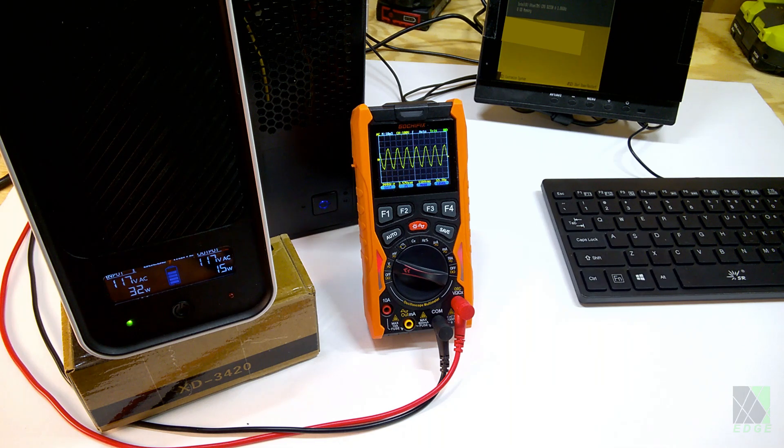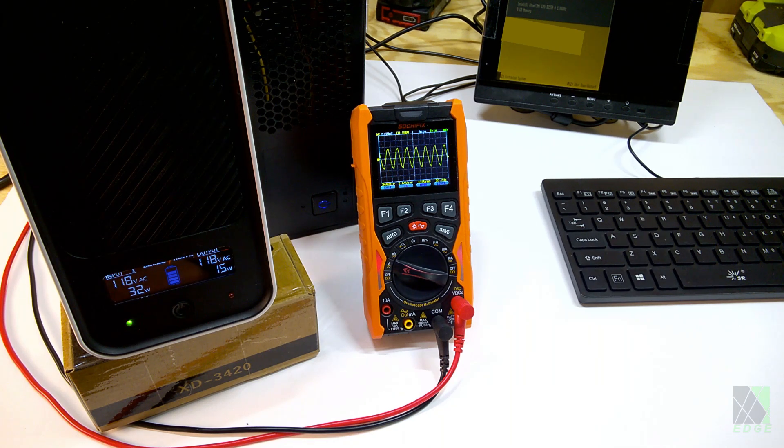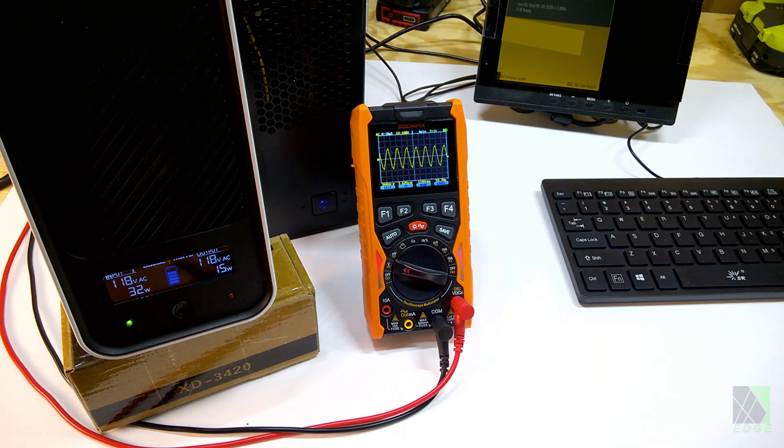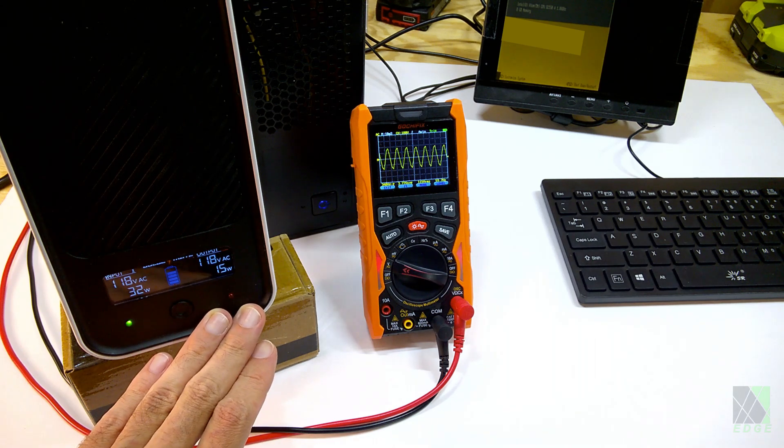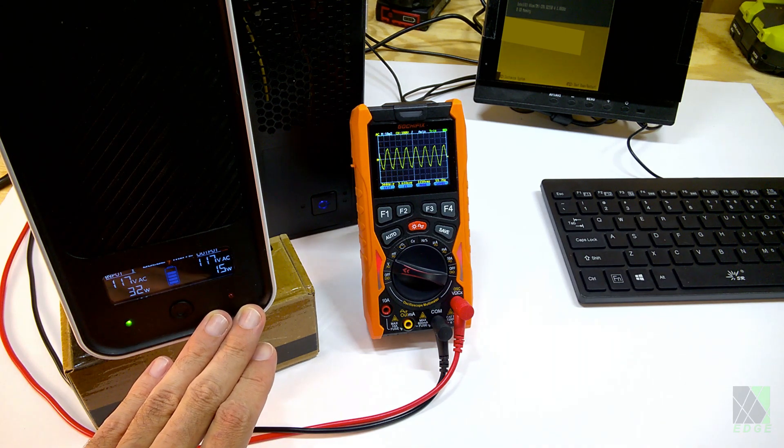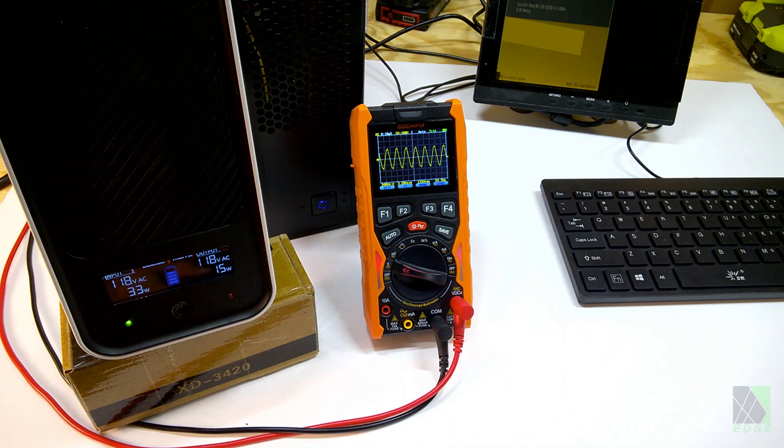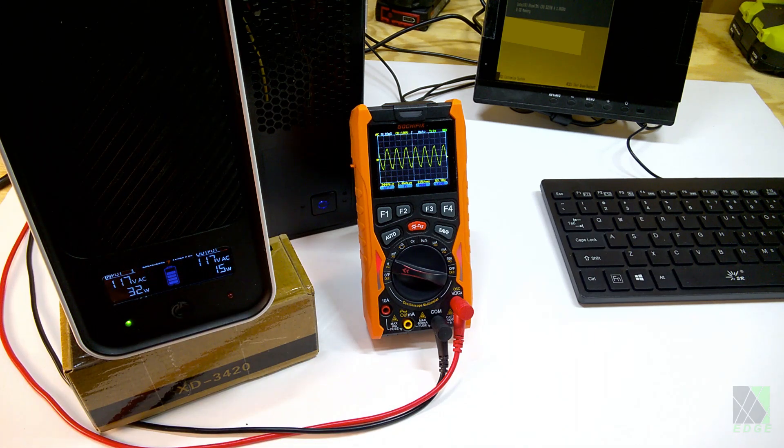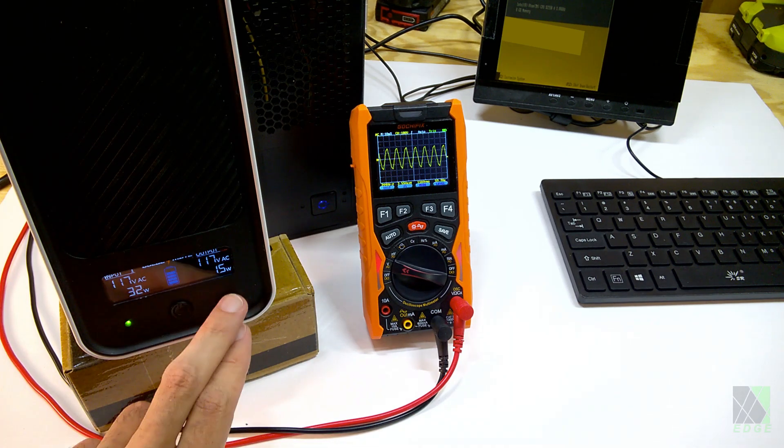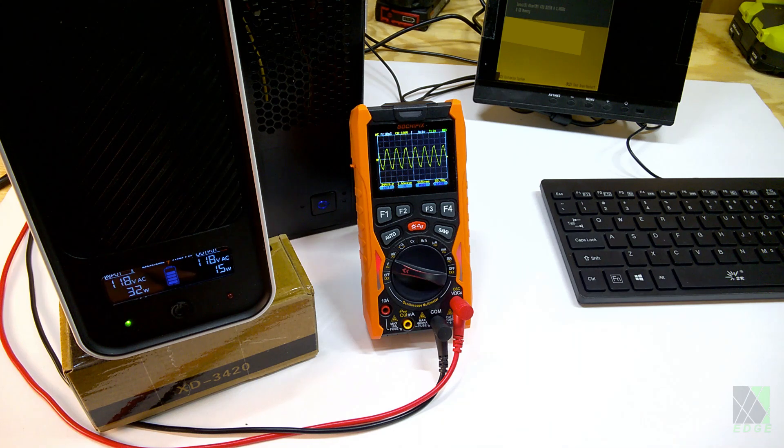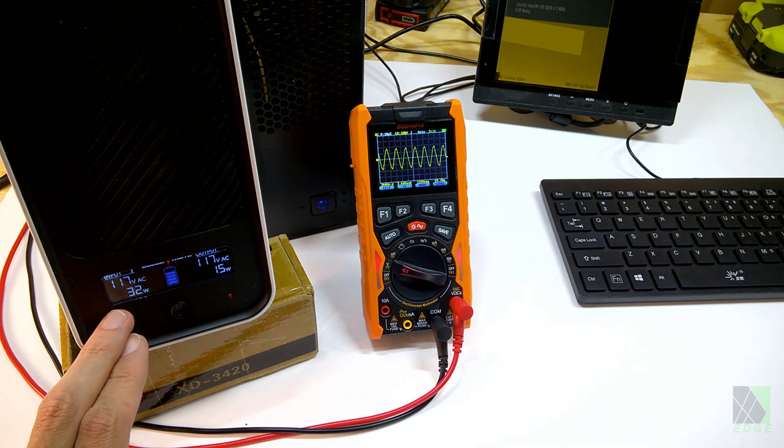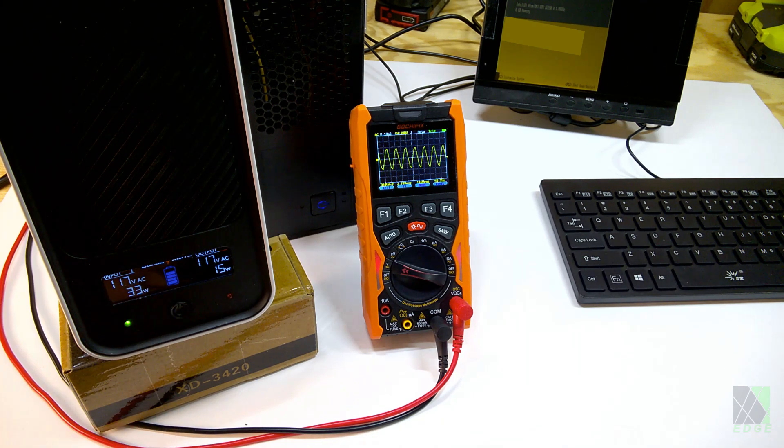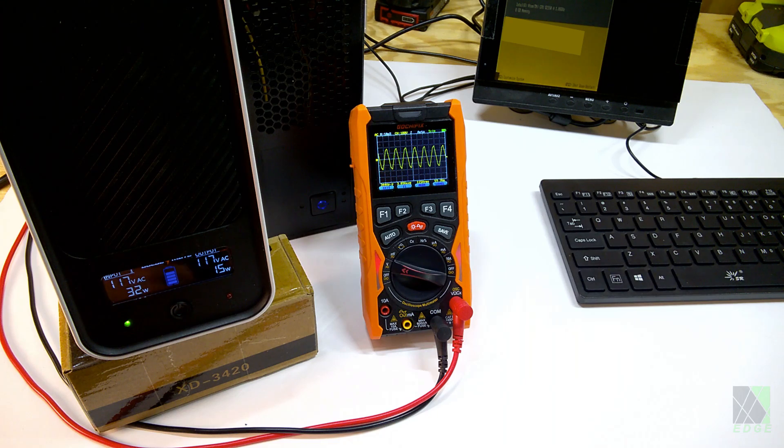I hear a relay click. Yeah, okay, there's a delay. It doesn't turn on right away, and believe it or not, that's exactly what you want. It's called hysteresis, and you don't want this UPS to instantly go back on to mains power if it comes back on, because what can happen is it comes on and goes right back off, and it could crash your system. It did exactly what I would like it to do. Then I heard the relay click, and there's no drama. It just works.